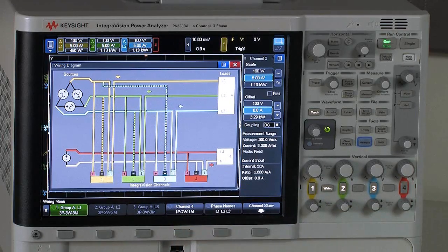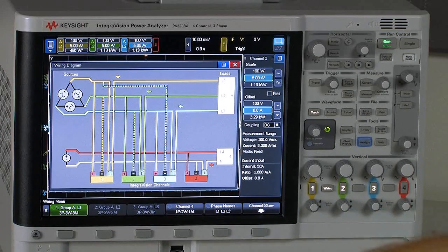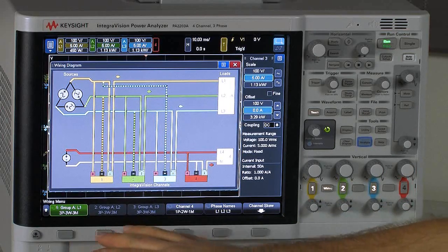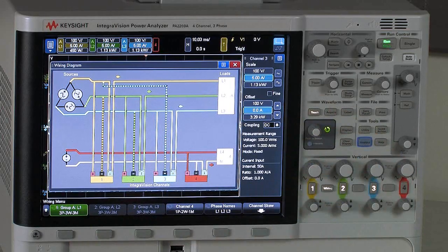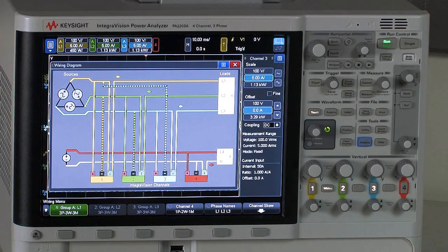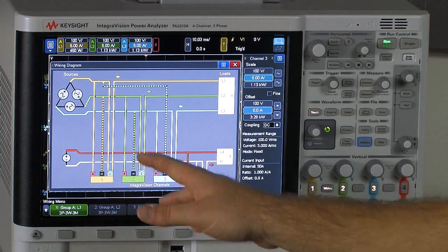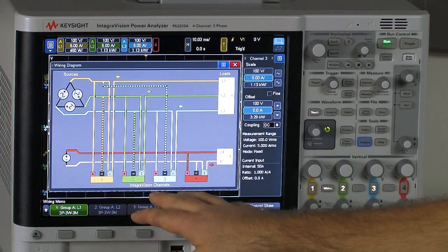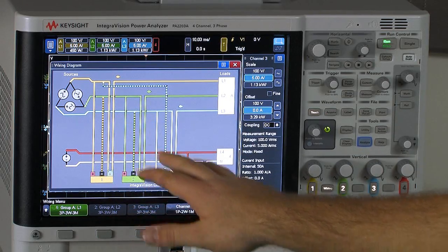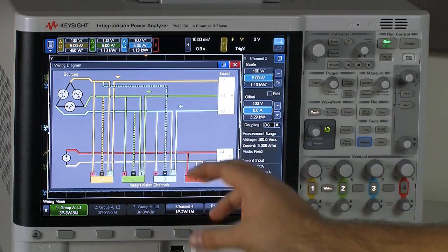So what we can see, two things happened immediately here when I turned this group on, which is called Group A. First, the options for channels two and three are grayed out because channels one, two, and three have been grouped together. And then the other thing is we notice this wiring diagram now has been completely updated to reflect the delta wiring configuration I've chosen.